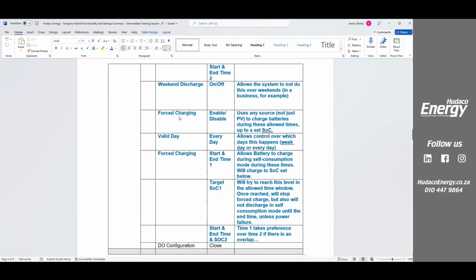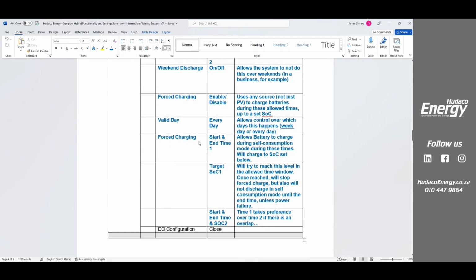Forced charging is exactly the opposite. Forced charging says, now unlike compulsory mode, which just tells it to do it, forced charging says, during this window, whatever time it is, I want you to check the state of charge on my batteries. If the state of charge on the batteries is below what you're setting for me, I want you to charge it either from solar or from grid. Okay, in fact, it's actually from grid. So if we turn forced charge on, we can say, do you want it weekdays? Do you want it every day? When do you want it? What time should I start? What time should I end? And what percentage should I go to?